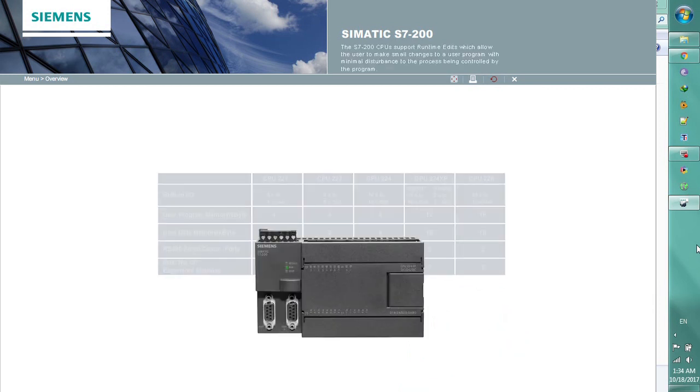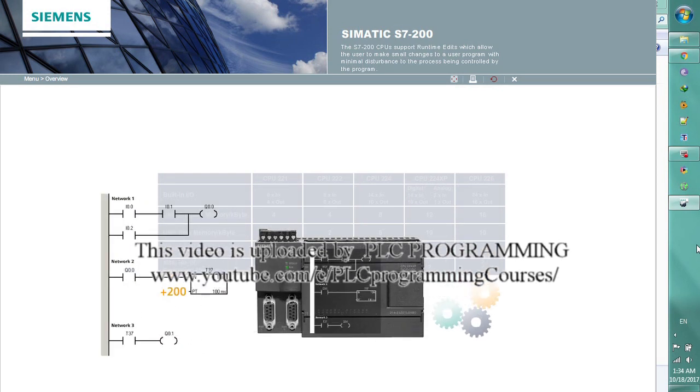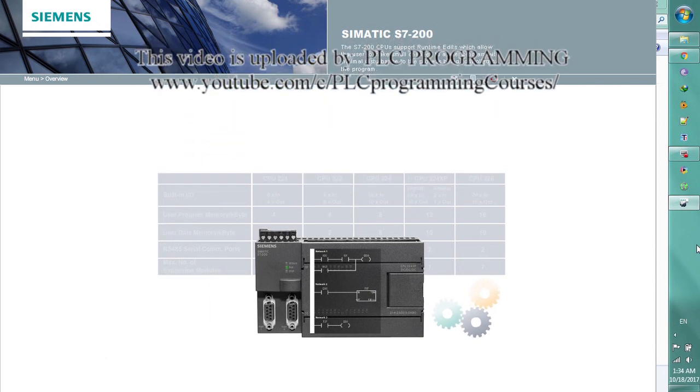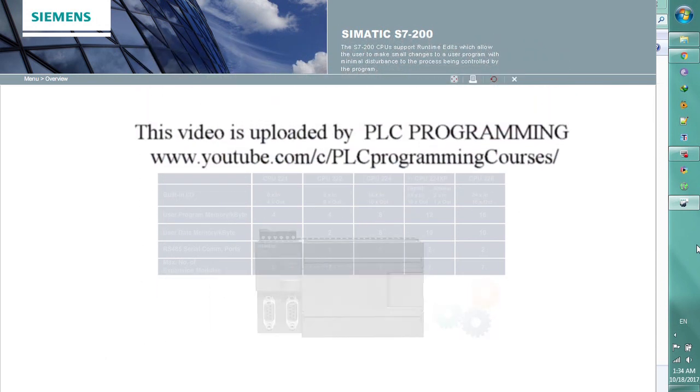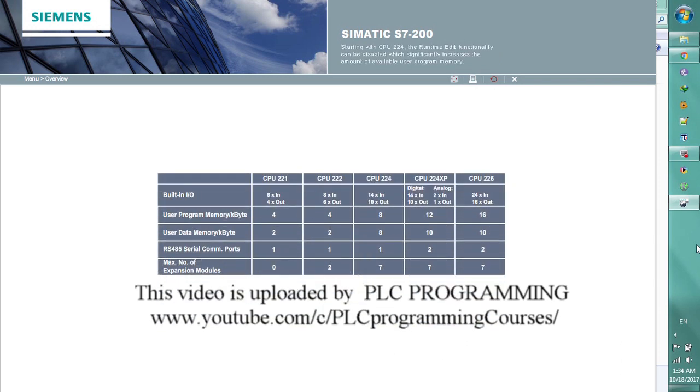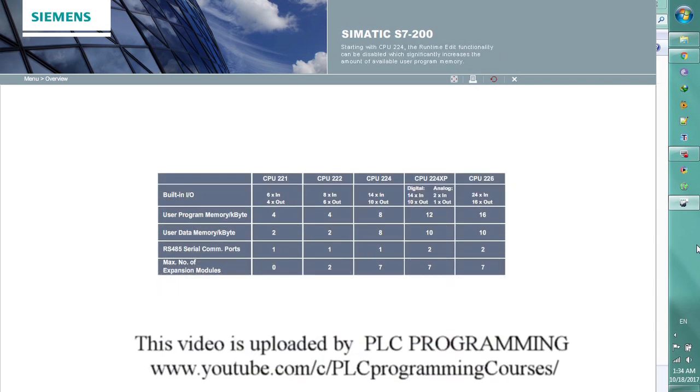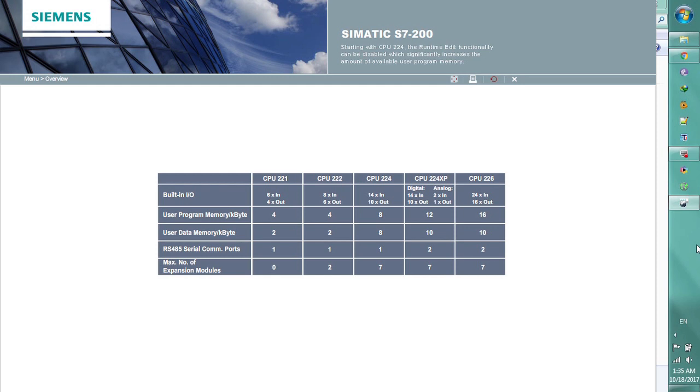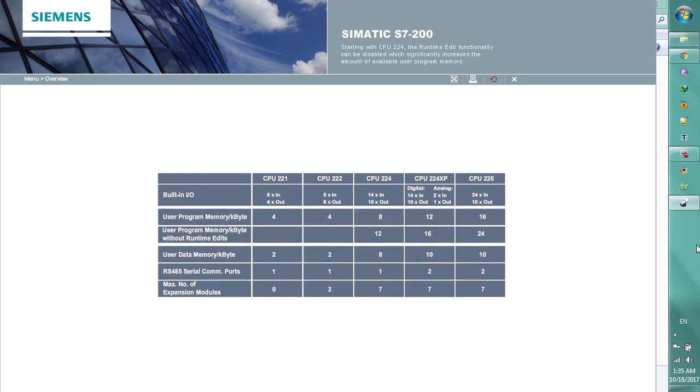The S7-200 CPUs support runtime edits which allow the user to make small changes to a user program with minimal disturbance to the process being controlled. Starting with CPU-224, the runtime edit functionality can be disabled, which significantly increases the amount of available user program memory.